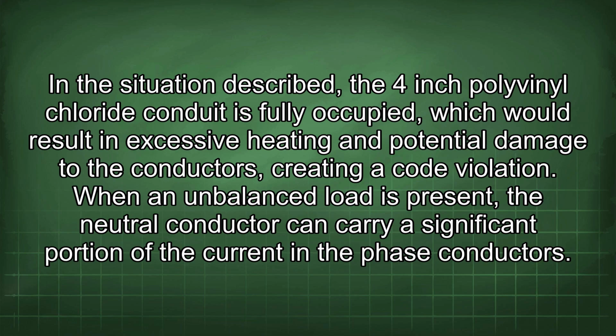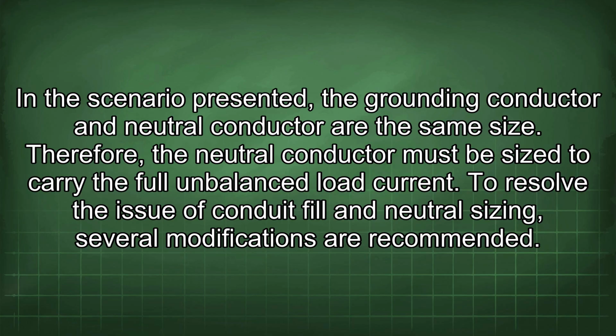When an unbalanced load is present, the neutral conductor can carry a significant portion of the current in the phase conductors. In the scenario presented, the grounding conductor and neutral conductor are the same size. Therefore, the neutral conductor must be sized to carry the full unbalanced load current.